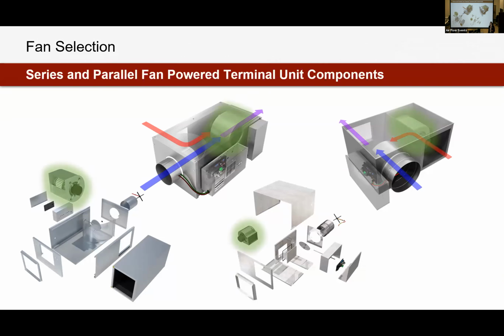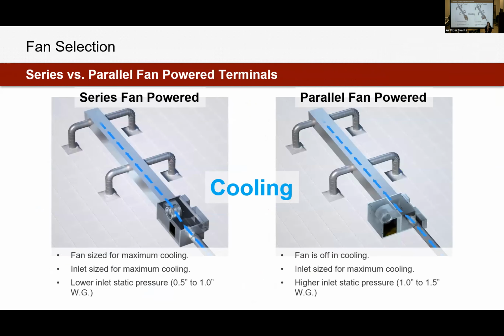So both types of units have a motor blower assembly. They both have an inlet valve. So this is what's ducted to our air handler. And they both have a return air opening. This is where we are inducing or drawing air in from our plenum. Now, what actually makes these boxes different is their configuration. So in the series box here, this is called series because our inlet valve is in series with the fan. They're in line with each other. Your fan is located on the discharge in a series box.